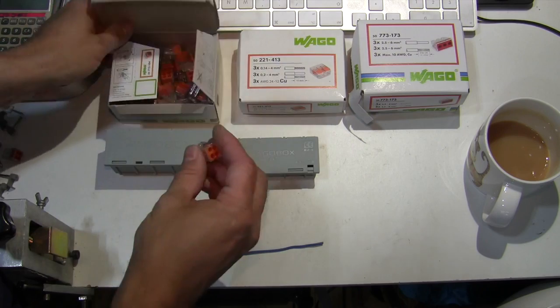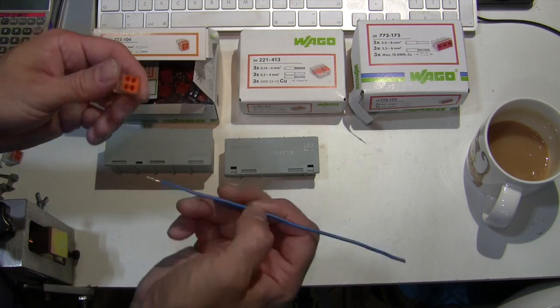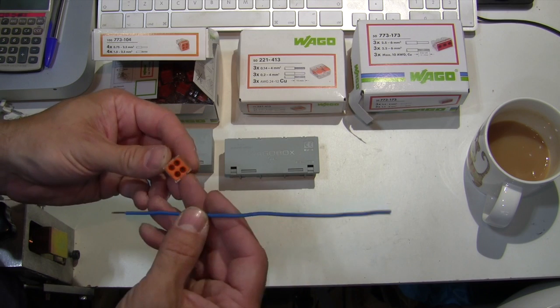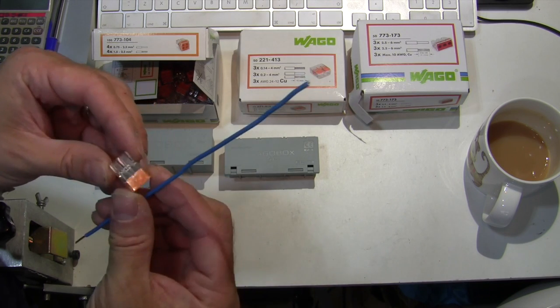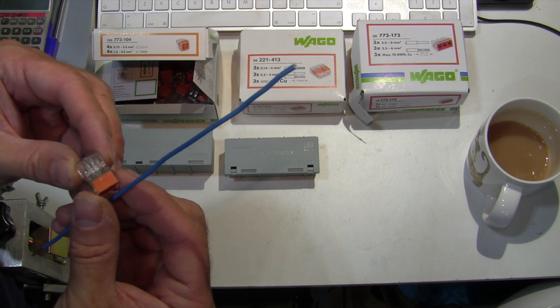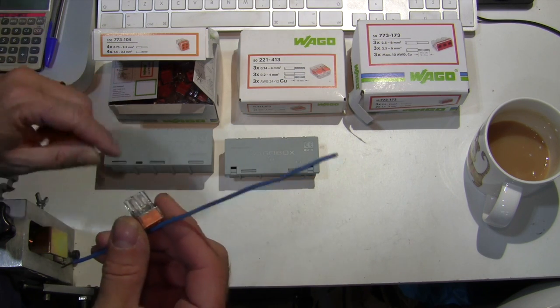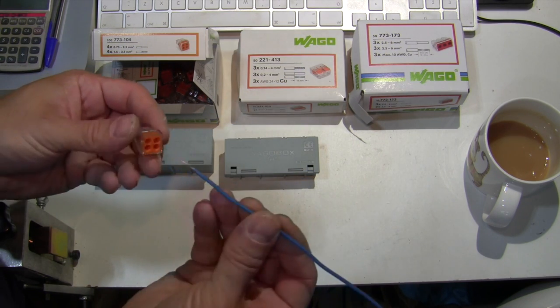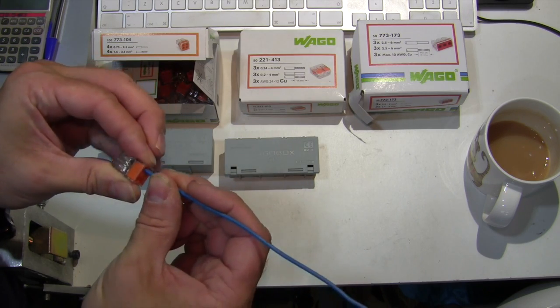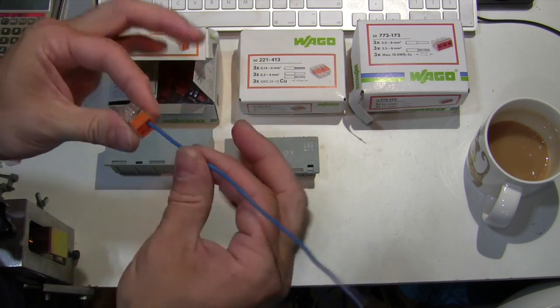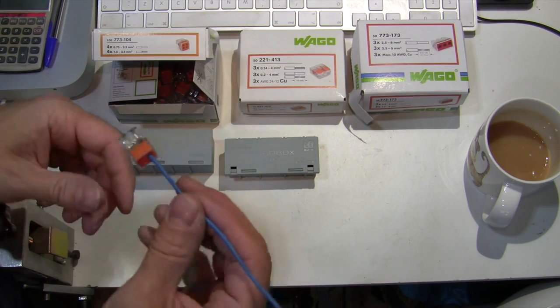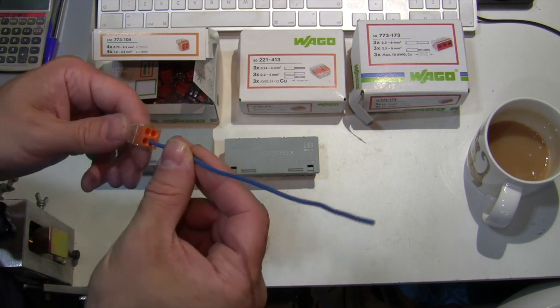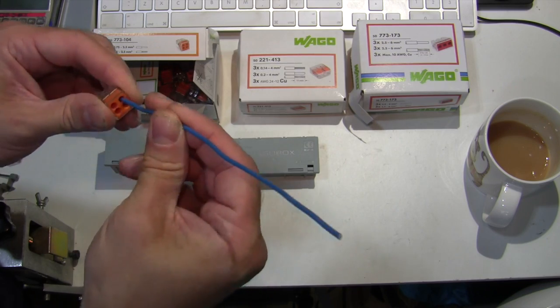these are push-fit connectors. This particular one is a four-way, so four wires can go in there. It'll take one mil to up to 2.5. So I've got a bit of one mil here. And when you push it in, the spring clip holds it in, that ain't going to come out. And unlike a screw terminal which can work loose over time, that's considered to be a maintenance-free connection.